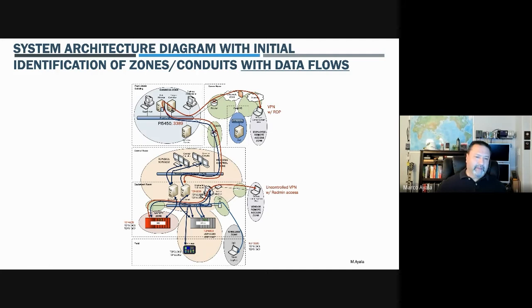What you will find is that whenever you're capturing this data, one clear thing to note is that it may make sense to make sure that whatever you're capturing communication-wise is actually sent out-of-band of your own process control network and your own DMZ, or up to a DMZ from an out-of-band network, to make sure that you're not impacting that control network. Even though you're capturing east-west, you don't want to inject back into it all your mirrored port traffic. So just maybe having some out-of-band networking for that would be a good engineering choice.